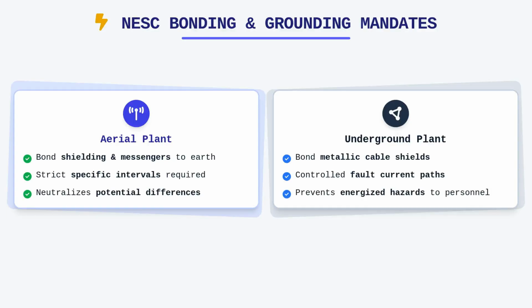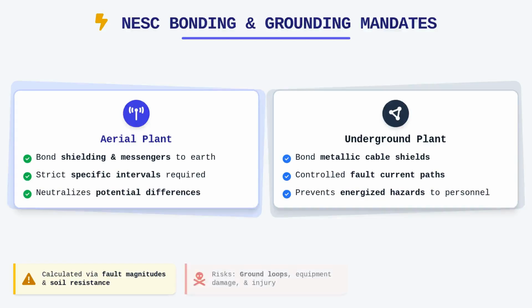These intervals are not arbitrary. They are derived from a deep understanding of fault current magnitudes and the resistance of the surrounding soil. When you design these systems, you are essentially creating a safety shunt that protects sensitive information transport equipment from the catastrophic effects of power surges. If these bonding requirements are ignored or executed poorly, you expose the communication system to ground loops and safety violations that could lead to equipment damage or injury. Rigorous adherence to these grounding intervals is the final line of defense in maintaining a legally compliant and objectively safe outside plant design.